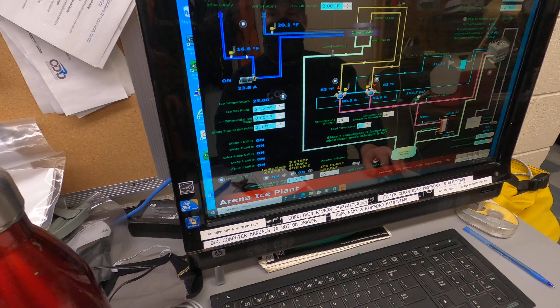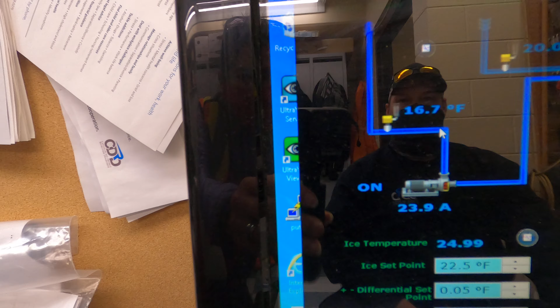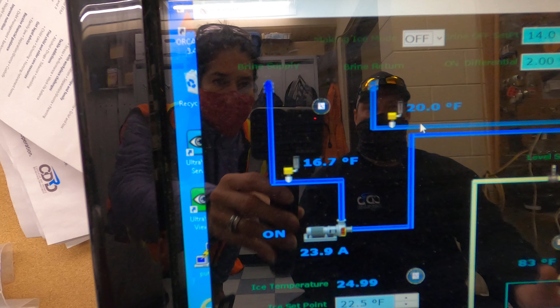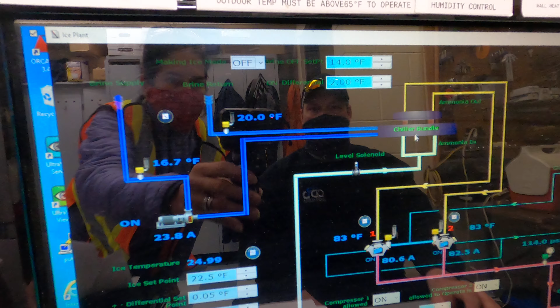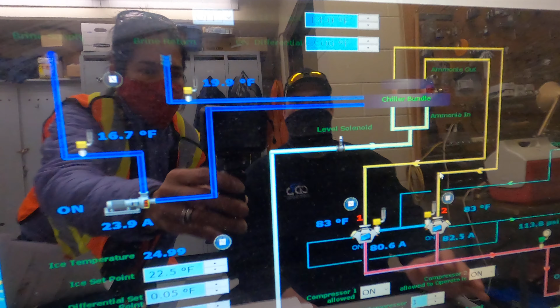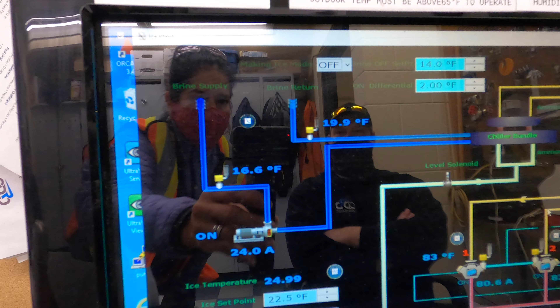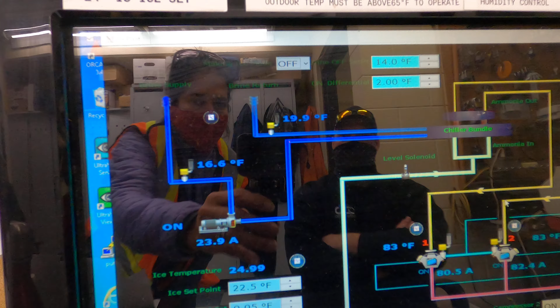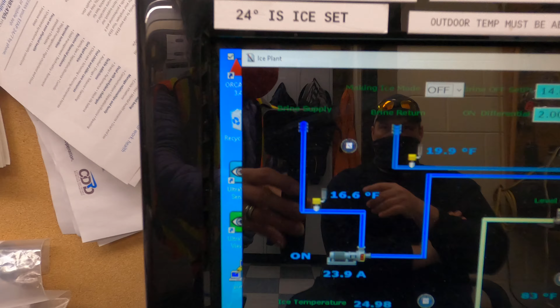Oh, nice. Yeah, and then these are just my supply and return temperatures over here. So this is representational of the brine pump. It's going out to the arena at 16.7, and it's picking up just a little over 3 degrees Fahrenheit, which is great. That's what you want to see. And then just showing that it's coming back into the chiller. My ammonia liquid is coming into the chiller, and my ammonia gas is coming out of the chiller going to the compressors. So the brine comes in at 19.9 right now, or 20 degrees Fahrenheit. Correct. And goes out at about 16.6.